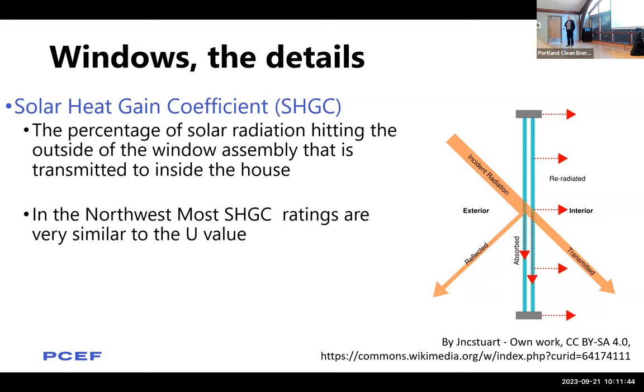A really, really big difference. So say I have 100 square feet of west facing glass, and there's a Walmart 10 feet from my house. How much solar radiation is going to hit that glass? Not much. You can account for that in your heat gain calculations. The Manual J process, which again is addition and multiplication, has been proven to oversize cooling loads by about 20%. The thumb is already on the scale. You do not need to put your foot on the same scale, or you're really oversizing, okay?